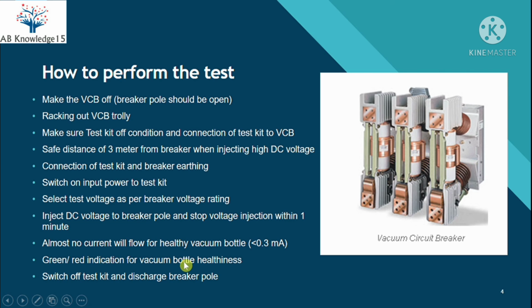In this way, after carrying out the test on the first vacuum bottle, you can carry out the test on the second and third bottle, and so on. Switch off the test kit and discharge the breaker pole at the end of the test so that the breaker pole is discharged from DC voltages.